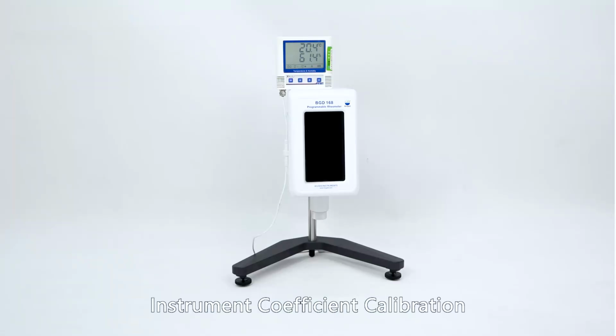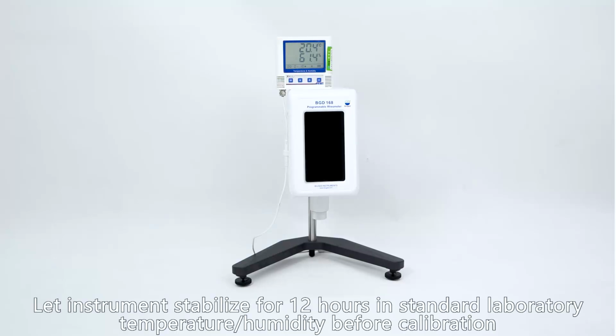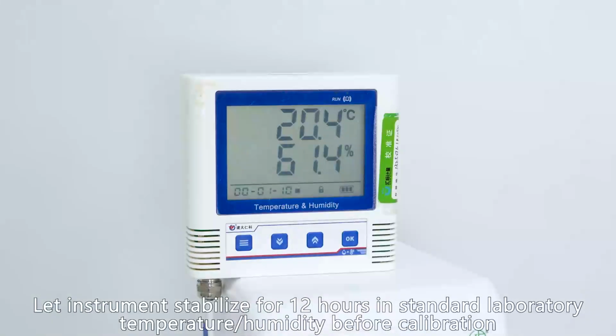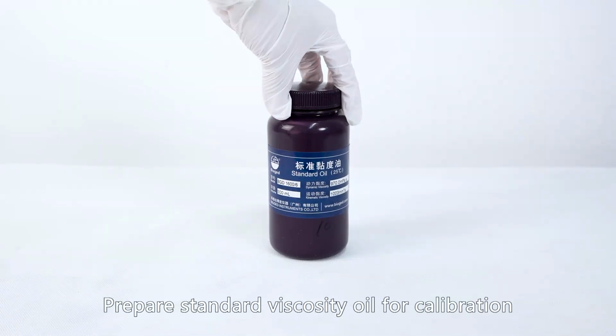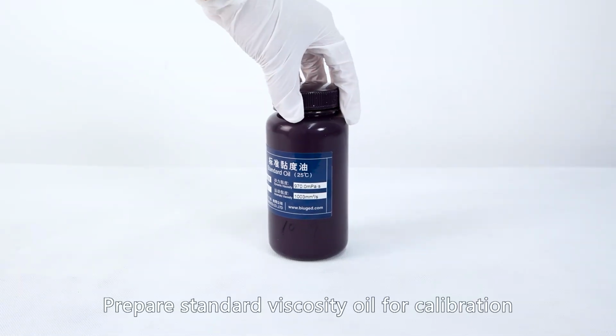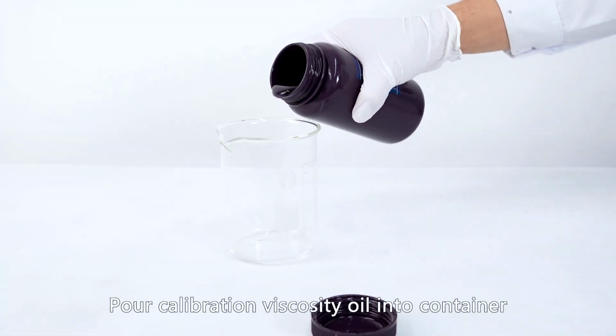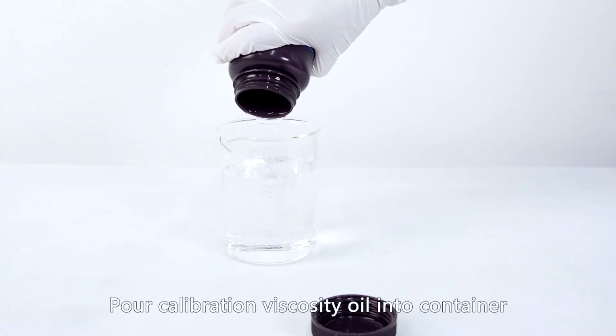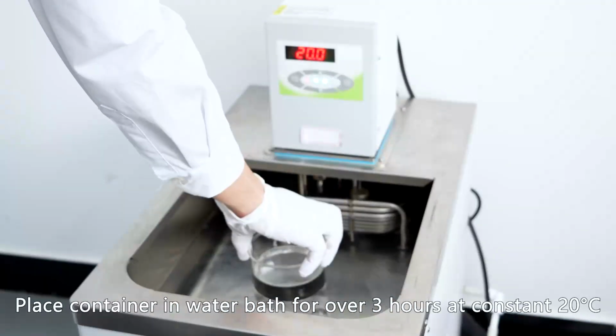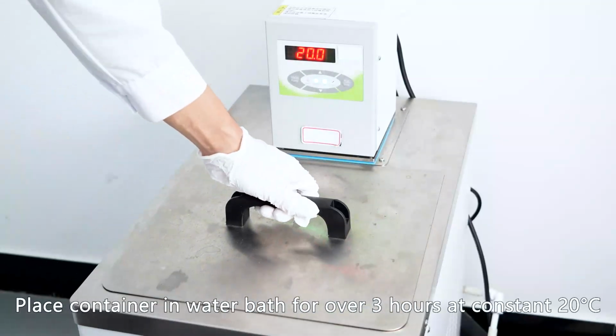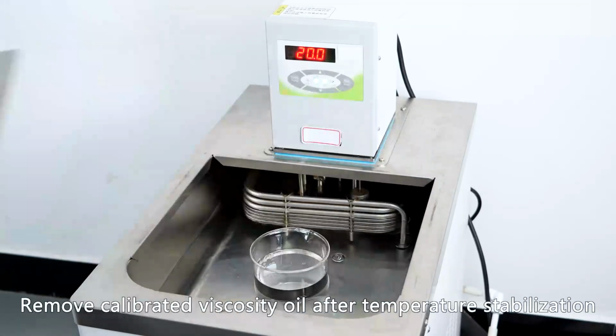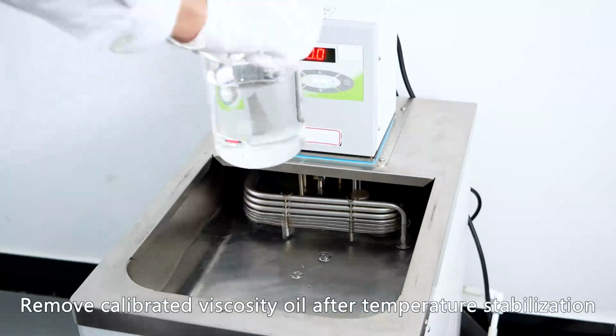Instrument coefficient calibration. Let instrument stabilize for 12 hours in standard laboratory temperature/humidity before calibration. Prepare standard viscosity oil for calibration. Pour calibration viscosity oil into container. Place container in water bath for over 3 hours at constant 20 degrees Celsius. Remove calibrated viscosity oil after temperature stabilization.